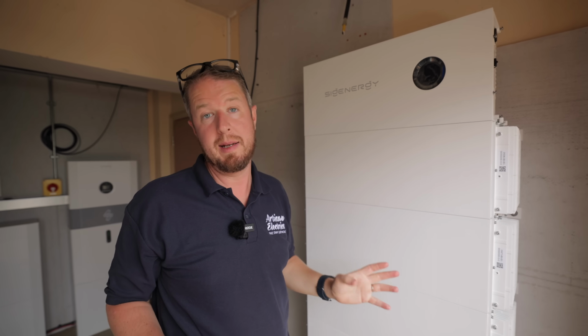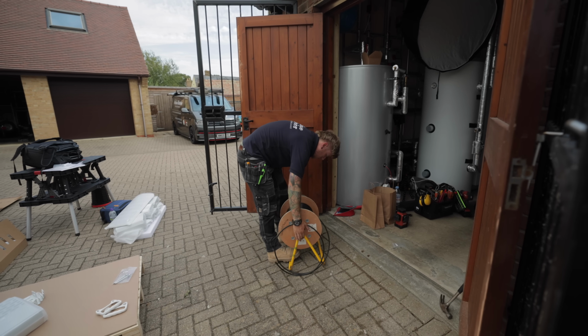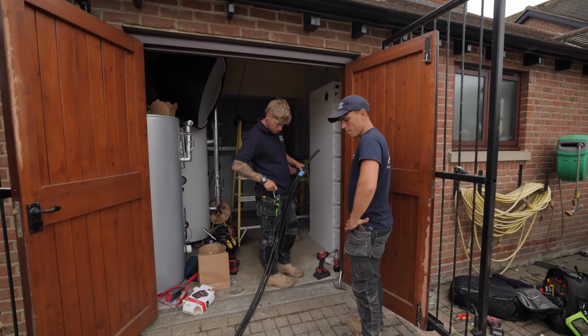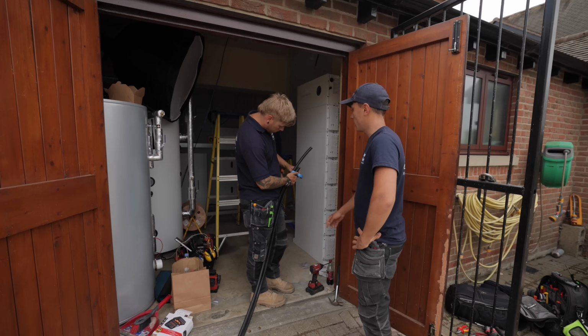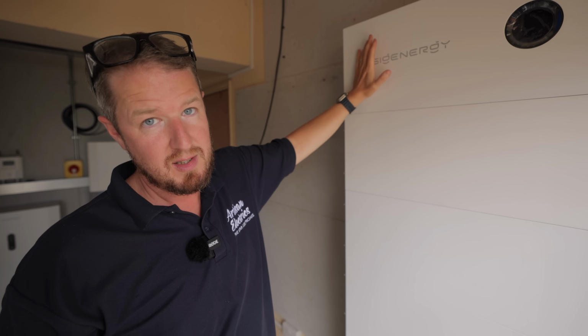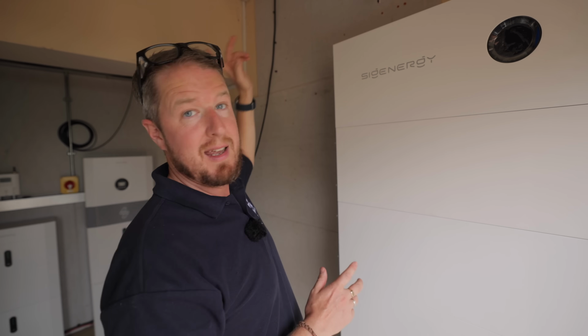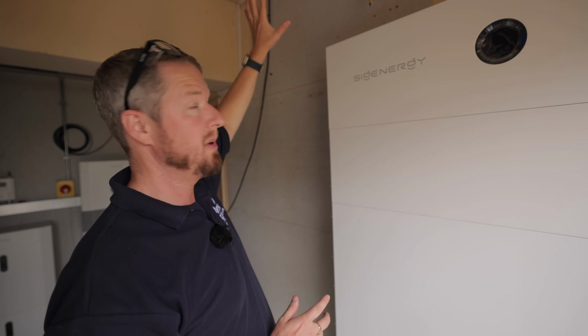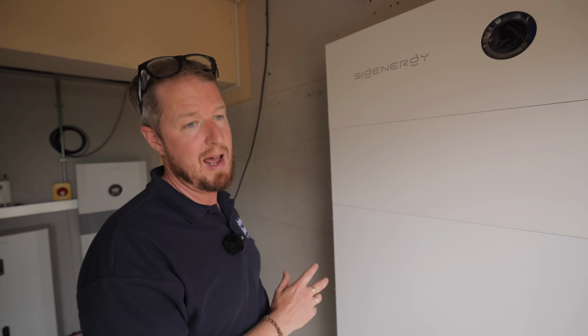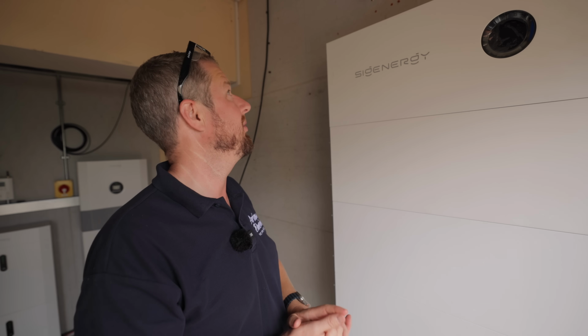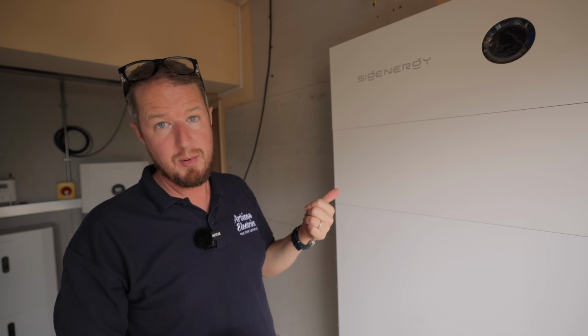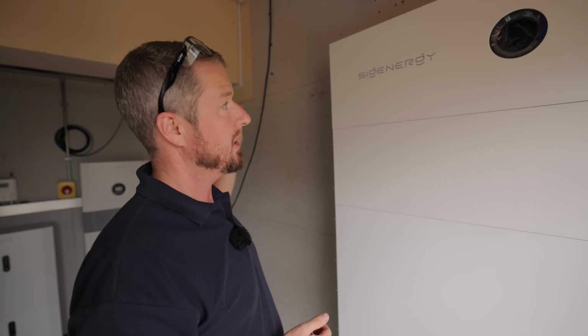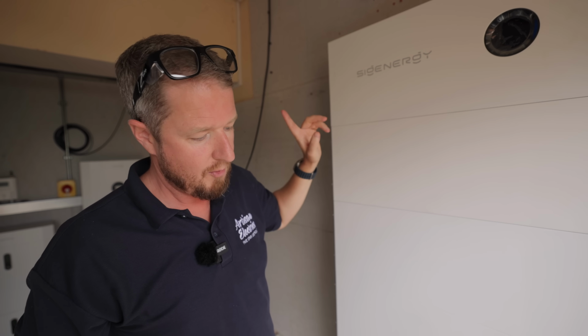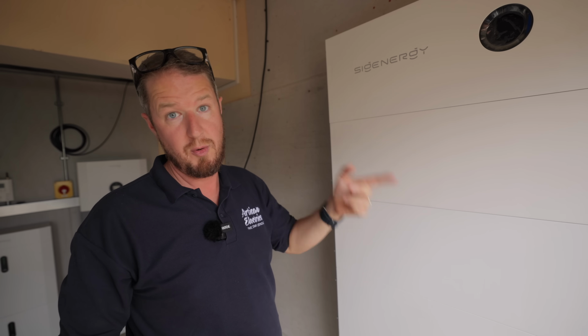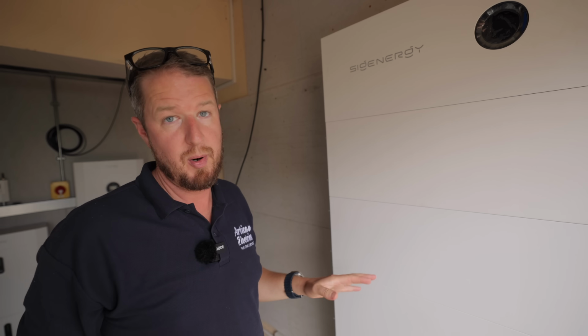Now that the stack is up, with the inverter on top, it's all about cabling. We're running two new power cables from here because the old one was just 6mm cable. We're running 16mm cable in for this because it's a 25 kilowatt inverter, so it can use a lot of power. We're also running a second cable for the future second stack so we can put the AC isolator in place ready for it, to make our lives easier when we come back and install that later. We've got a data cable to go in as well, a hardwired Ethernet connection, and an earth cable back to the main earthing terminal from the earth rod to give a full backup earth for the property.